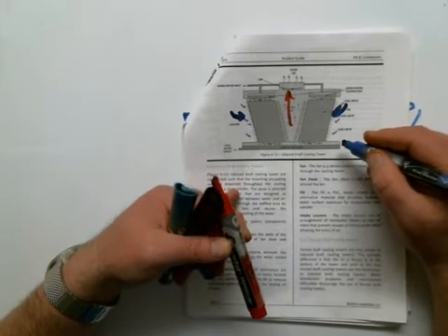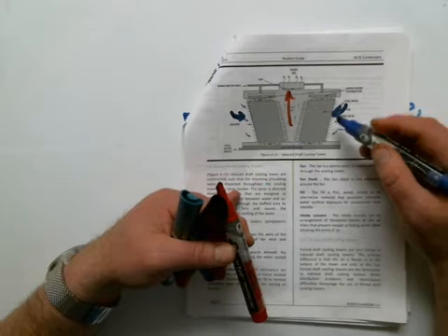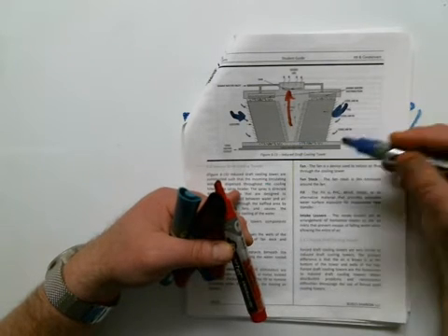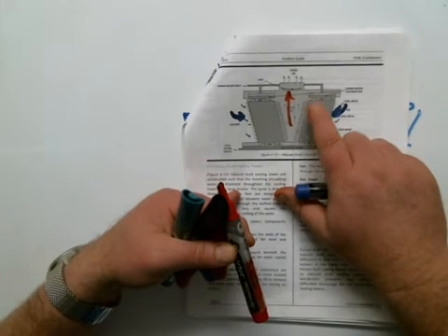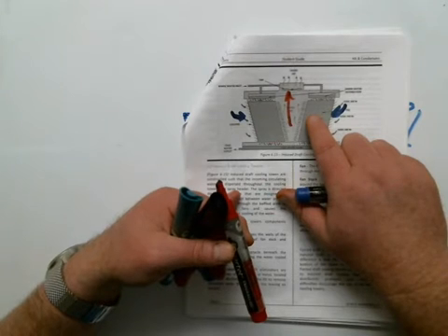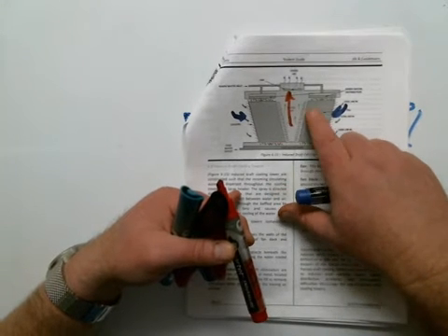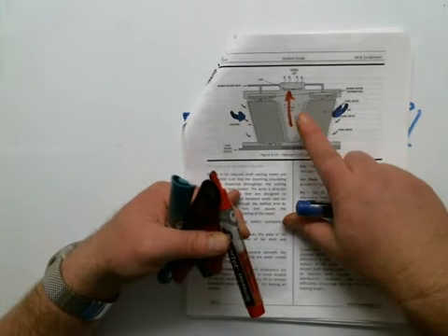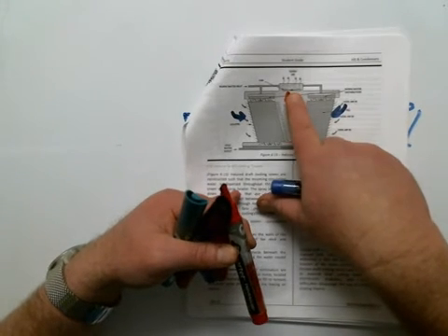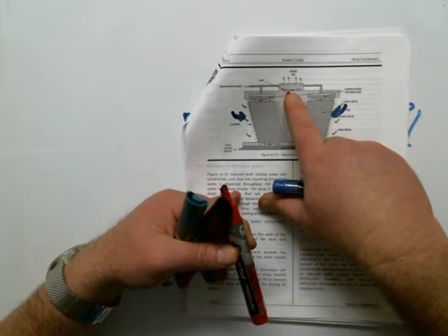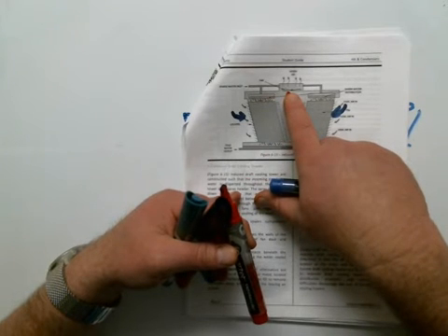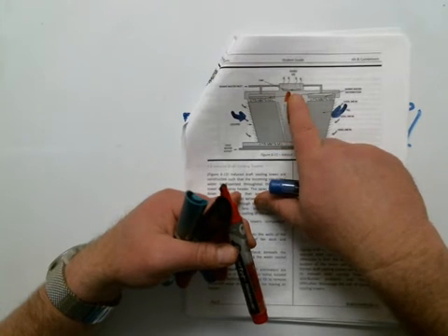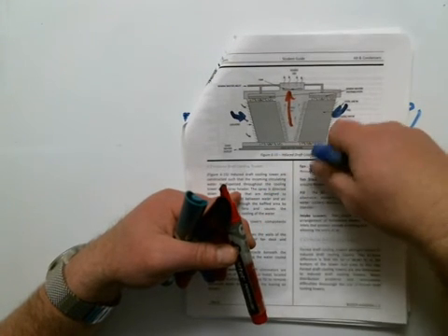Now very often when we're re-injecting our circ water back into a river for thermal pollution's sake, we'll use this type of cooling tower prior to returning the water back to the river to minimize our thermal pollution. So very similar to the natural draft, except that I actually have an electric fan. Very often this fan is a variable pitch blades, and setting them up can be a little difficult during construction, but pretty simple design actually.